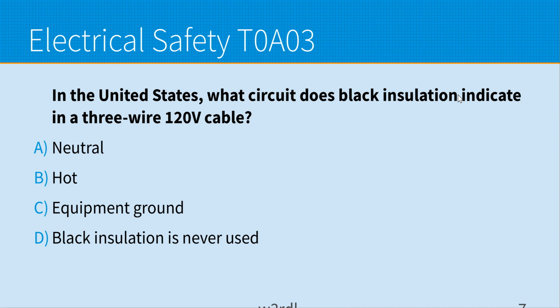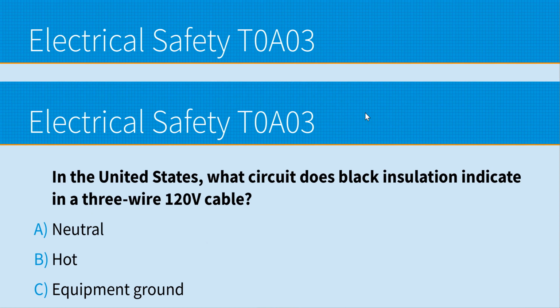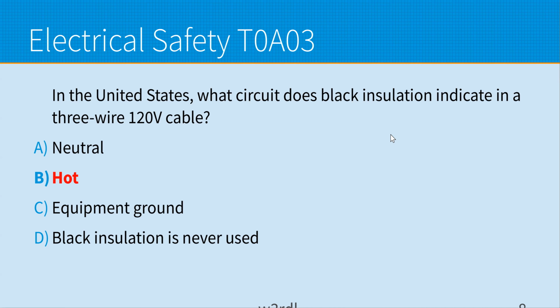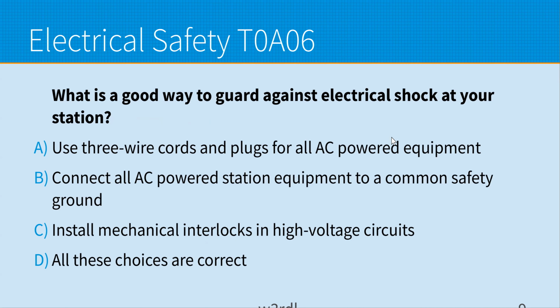If you have 240 volt, you have two hot lines. So one will be black and one will be red. And they distinguish them because they're 180 degrees out of phase. So you can't connect them together. It makes a big spark. So black is the hot.